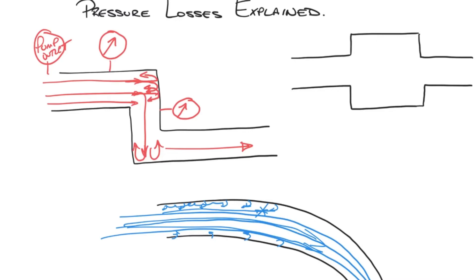This ends up being a pressure loss. The reason it's not called a flow loss is that if we don't give the flow another path to go, it has to get through the hose — it's going to continue going through anyway. All we see is that the effective pressure downstream becomes less.